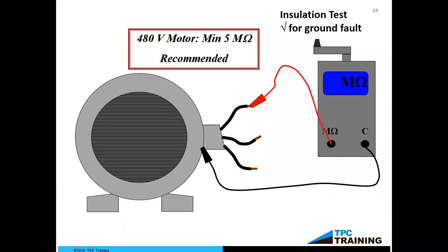But the higher that number, the better my insulation is. So the best number we could have, again, would be OL, or open circuit, which would just mean we can't force any electrons through the insulation on that wire. That means we have some great insulation.